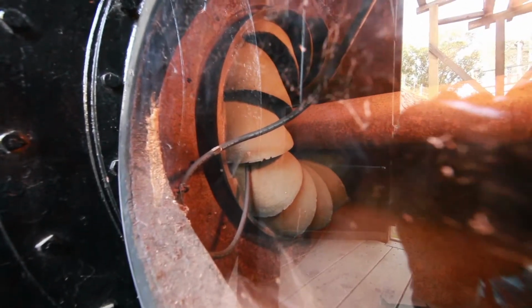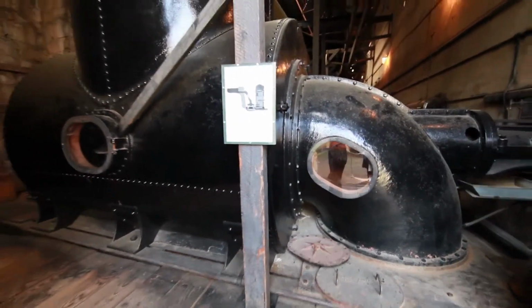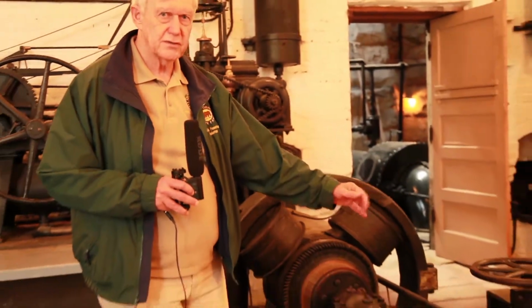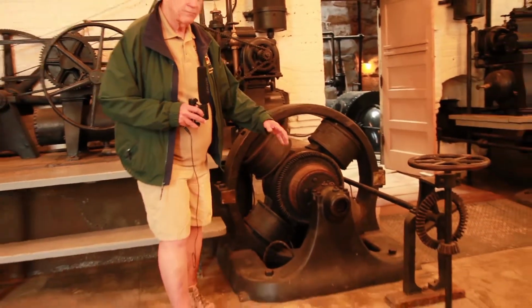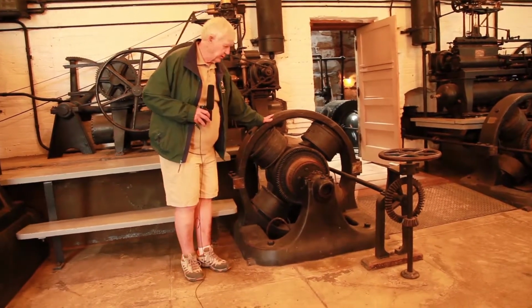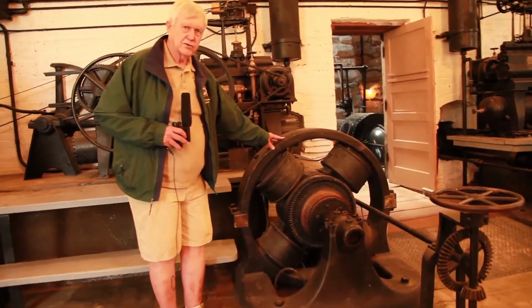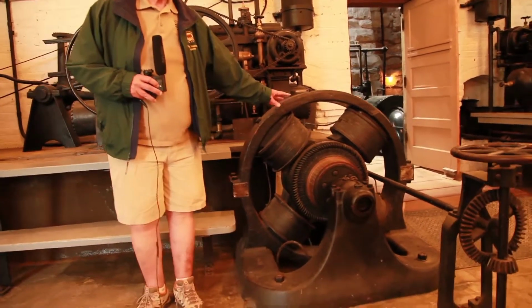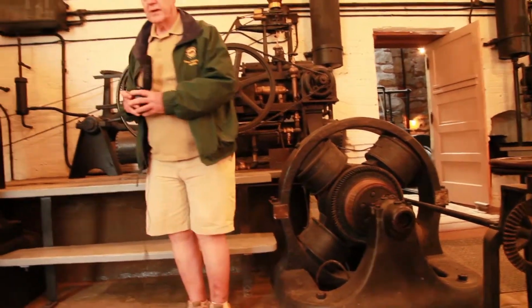This is a Francis-style turbine used for low-head applications. We only had about 57 feet of head in these turbines. They're bronze, and as you can see, there was one on this side and one on the other side of the turbine. To start up the powerhouse, the operator would first need to turn this wheel, which would open up the vanes inside the smaller turbine and give power to our exciter generator right here. This is a direct current generator, and it supplied power to the large alternating current generators.